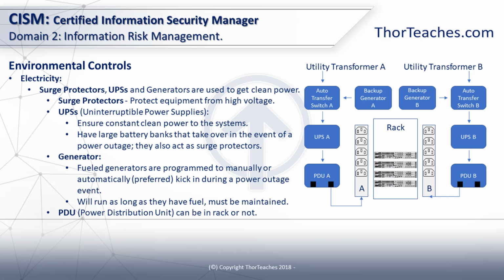Where we sometimes get into trouble is where we don't do the redundant power system, or we plug one server into just one side. So if we plug one server into A and something goes down in A, well, then the server goes down. So good power distribution really is part of our data center design. I think most of the stuff on the left we talked about already. The UPSs ensure the clean power and the battery, and they can also act as surge protectors at times. The generators are fueled and can either be set up to kick in automatically, or we might have to start them manually.